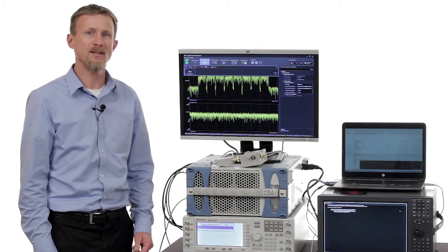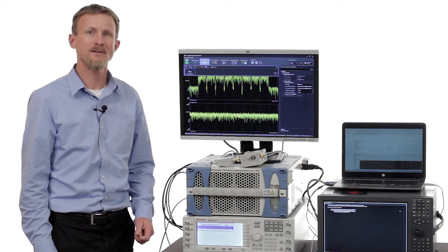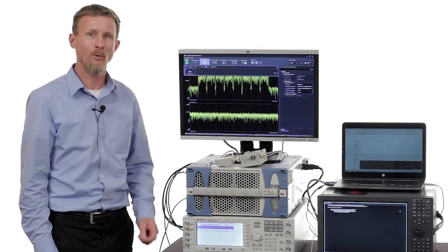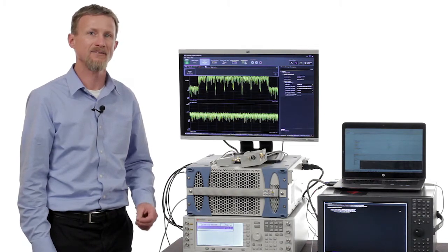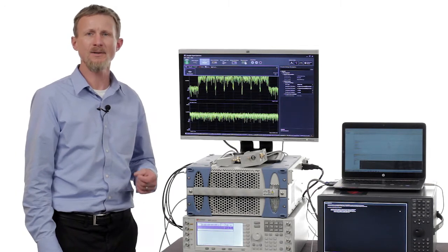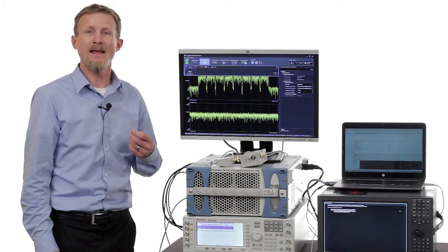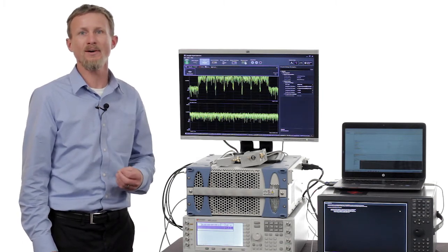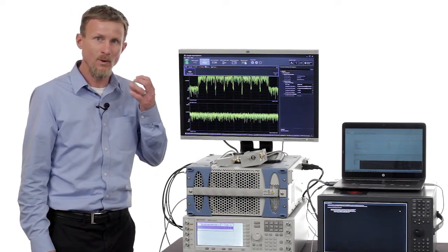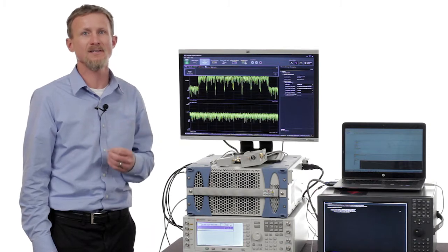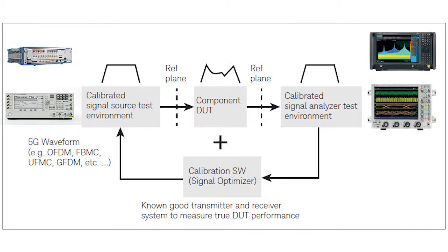The software does three important things: it can generate signals, it can analyze signals, and most importantly, it can calibrate right to the device plane of interest. Our customers have told us that calibrating is a big job for them. The reason this is important is that you want to see the true characteristics of your device under test — you don't want to see the characteristics of the cables, adapters, and test equipment. So we'll show you how to use the software to make measurements right to the device plane of interest.